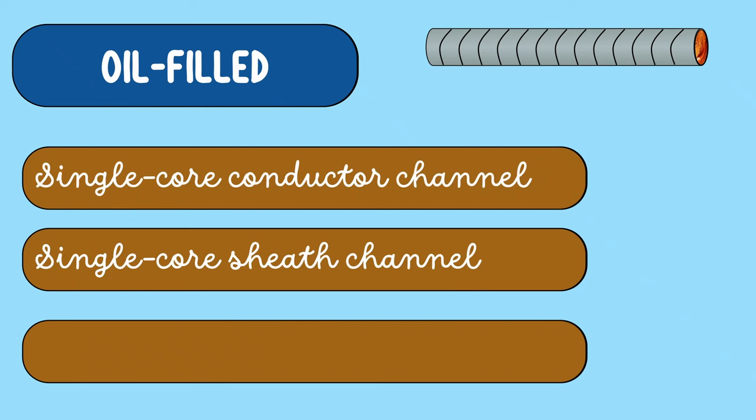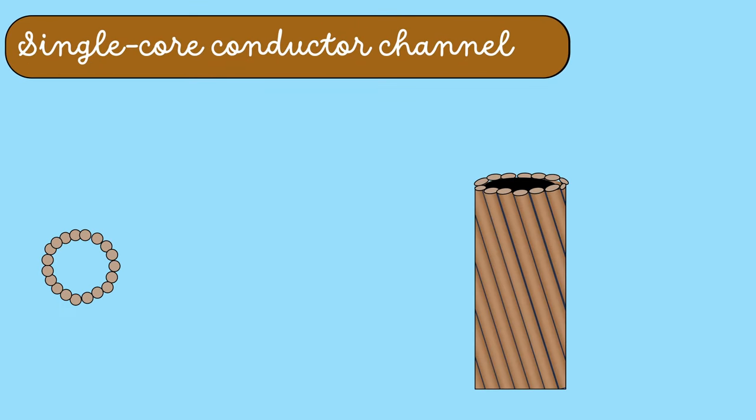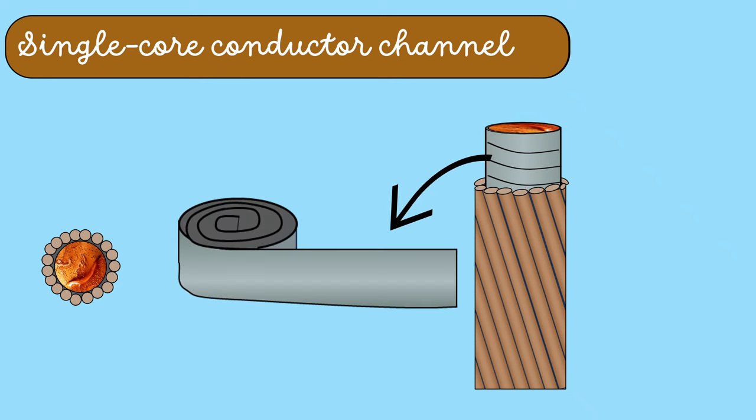Single-core conductor channel, single-core sheath channel, and three-core filler space channel. As the name indicates, a single-core conductor channel has one core. In this case, the strands of the core are arranged in such a way that it gives a hollow cylinder structure. Oil is present at the center surrounded by steel spiral tape.